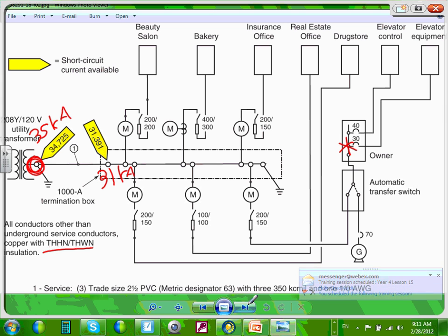So this value here, I'm just going to throw this out, could be as low as 22 kiloamps. What does that mean to you? It means the equipment downstream could be rated for a lower value. Cheaper equipment. Okay? Any questions, guys, about this? How did they calculate the value right at the transformer? You always start with the transformer. This is your start point.